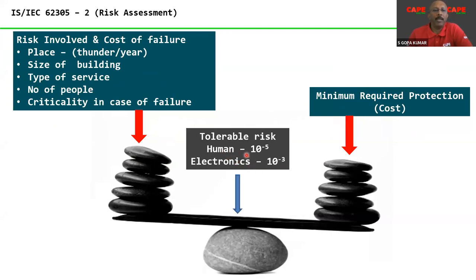For example, for human safety, 10 to the power of minus 5, in the sense, out of 1 lakh lightning strikes, one can be harmful to a human being. For protection of electronics, 10 to the power of minus 3, means out of 1,000 strikes, one can be harmful to electronics. So based on the tolerable limit on one side, and on the other side, the minimum cost which has to be spent for lightning protection, we make an assessment and find out, number one, whether your building requires lightning protection or not. Number two, what level of lightning protection is required if LPS is necessary.